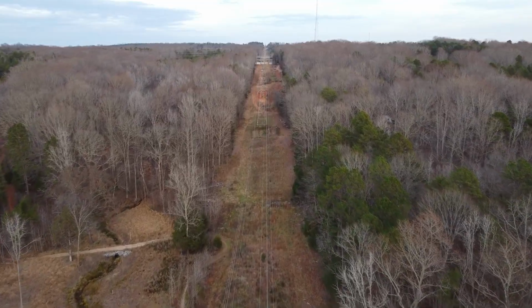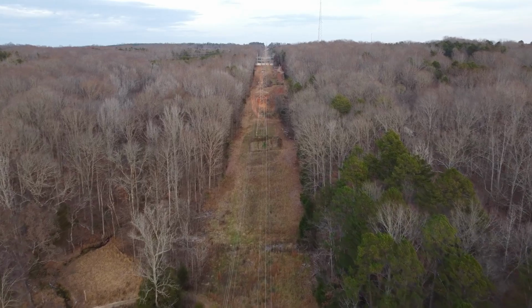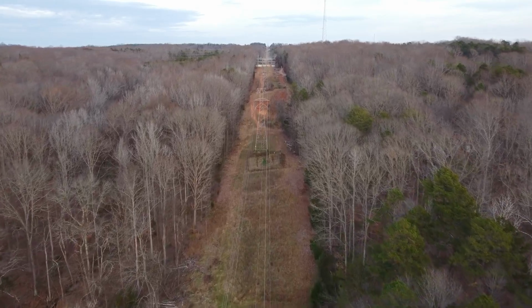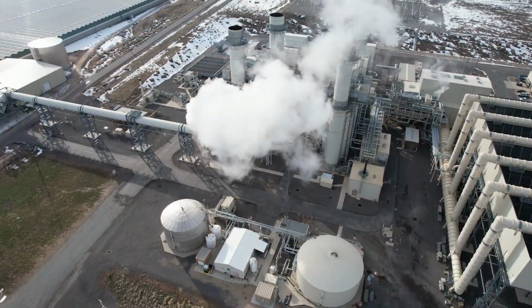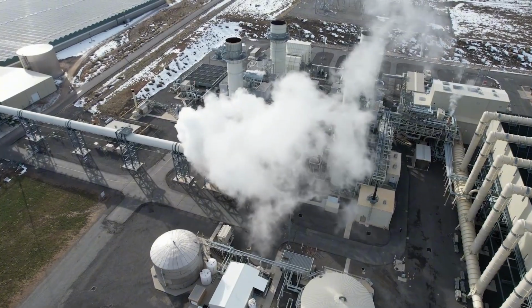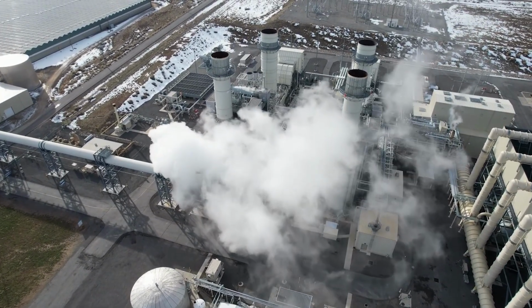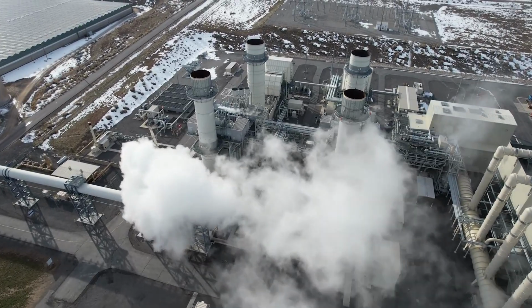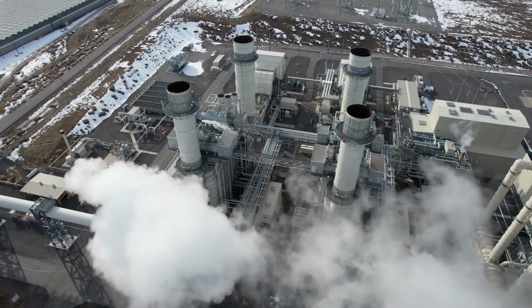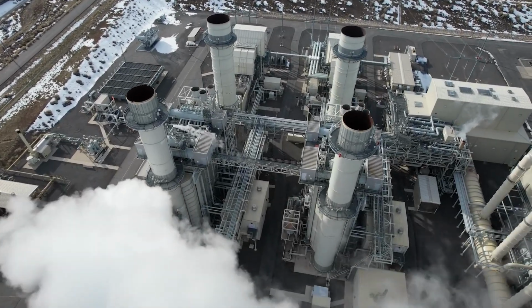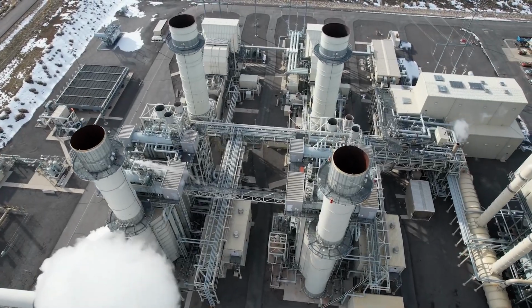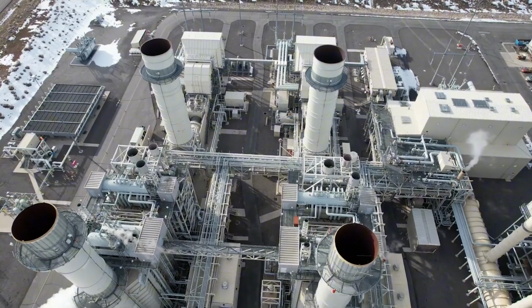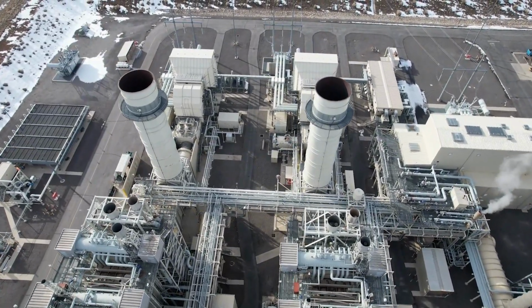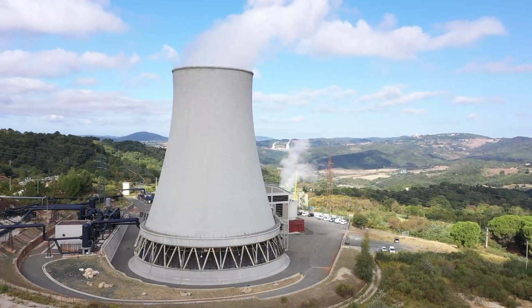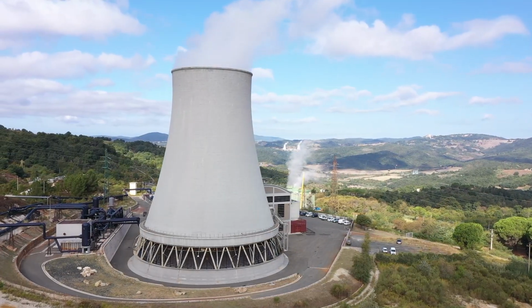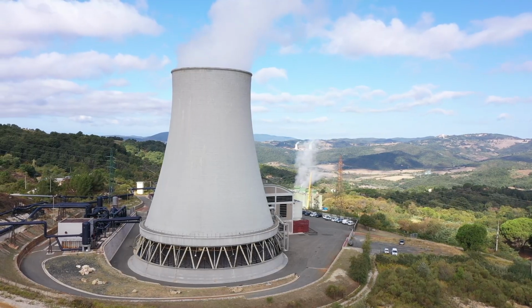Applied to the grid, N-1 means that transmission planners model every component in their system and simulate its failure. They remove a line from the model and ask, do any remaining lines overload? They remove a transformer and ask, does voltage collapse in the region it was serving? They remove a generator and ask, does frequency stability hold across the interconnection? If the answer to any of those questions is yes, the planners are required to fix the problem before it becomes real, either by adding capacity, rerouting flows, or installing new equipment. It is a serious and disciplined standard.